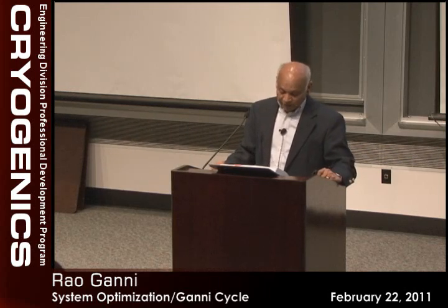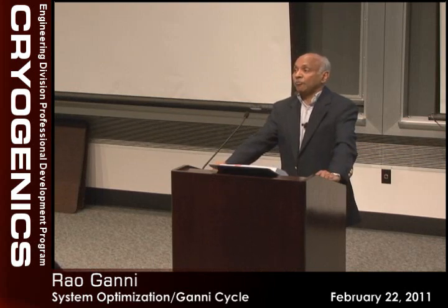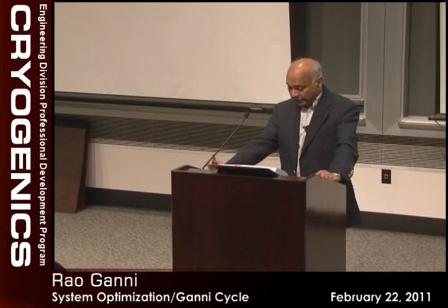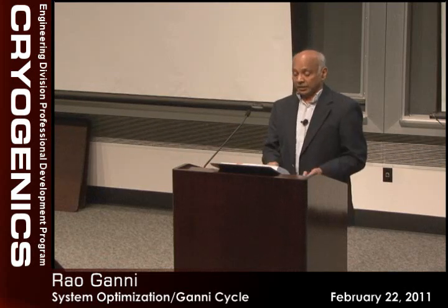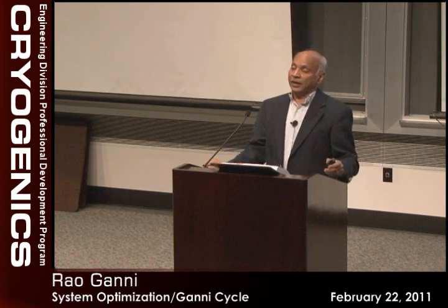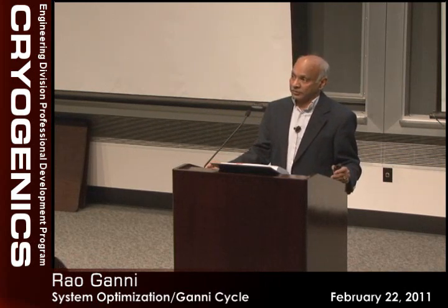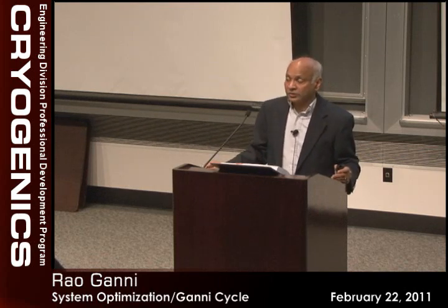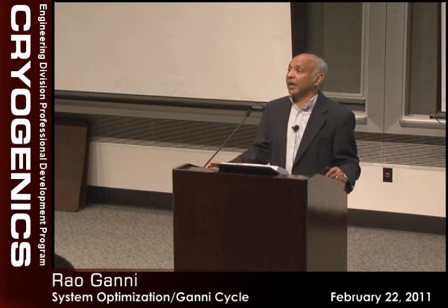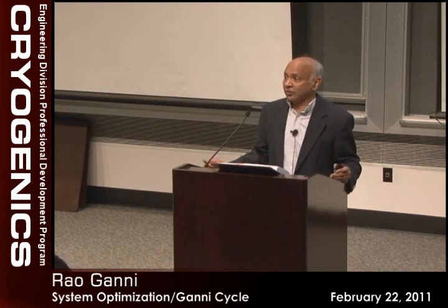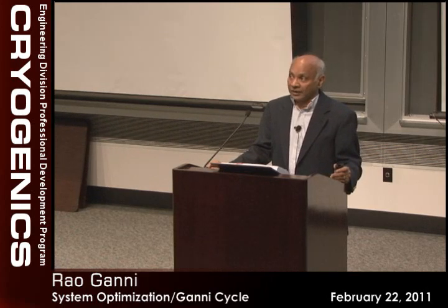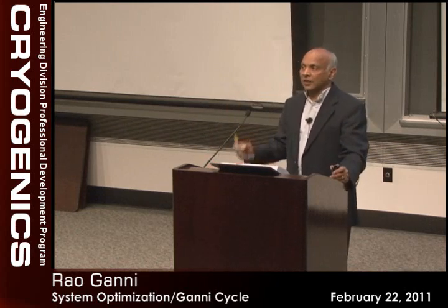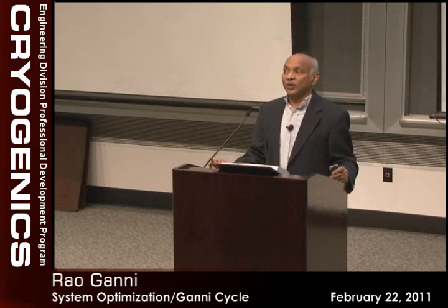What we found, when we reach these high effectiveness levels, we have to pay very high attention to analysis and quality control in defining the distributors, the nozzles, the mass distribution between stacks. Like we have heat exchangers with say 20 layers on the high side and 50 layers on the low pressure side. And one layer malfunctions, you lose 5% of the effectiveness right there. That means you started with 100, you're already at 95. And in the helium business, if 98 or 97 is the lowest, after that your capacity will start dropping very quickly. Whereas in process industry, if a leak develops, you just plug the one pass. You can't afford to do that in helium.